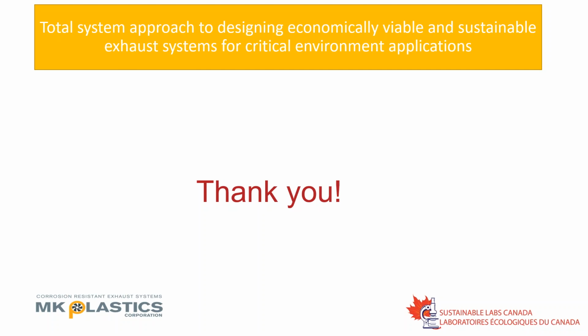Okay. Another question. Doug, thanks for your presentation. Do you still see many constant volume applications versus VAV? So I do see a number of constant volume, but they are being reduced since ASHRAE 90.1 is basically encouraging or stipulating people to go to VAV controls. And as the air changes from the laboratory area are now being combined with the exhaust fans, the VAV controls is becoming more and more integrated with the lab exhausts. So while I am seeing some constant volume, I would say it's in the lower numbers compared to the VAV.